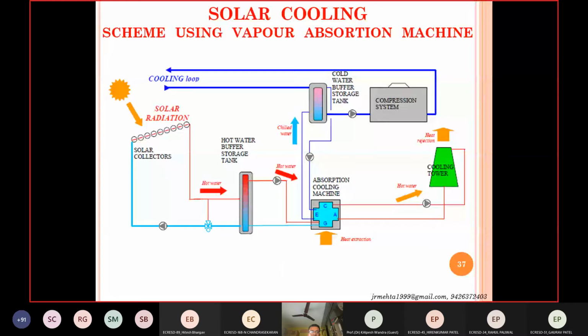So this is giving an overall system for a vapor absorption refrigeration system combined with the solar collector. So solar collector, then storage tank, then different components of the absorption machine, and the cooling tower required for providing cooling in the condenser, the chilled water generated here, and there could be storage of that, and you may have to combine it with the regular compression system, right? So for further cooling, and then this is the cooling loop. Okay.